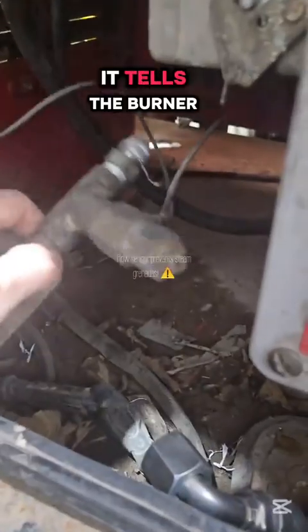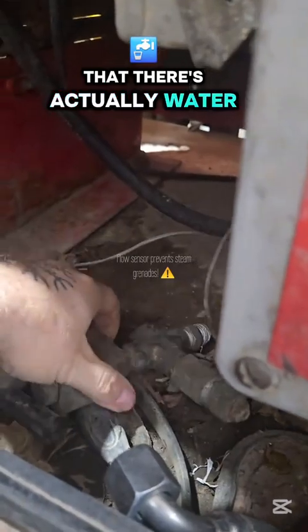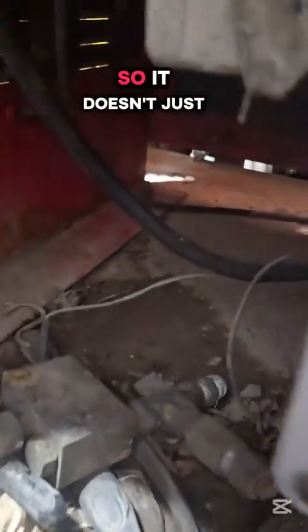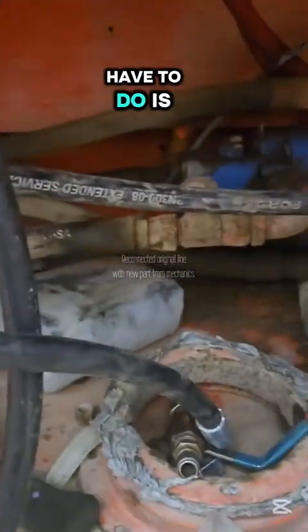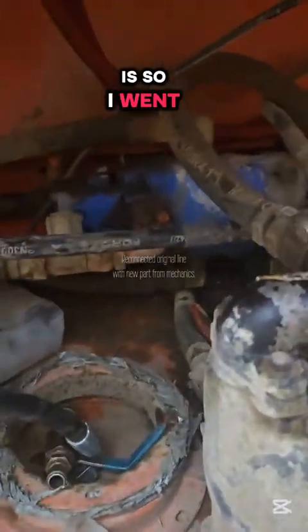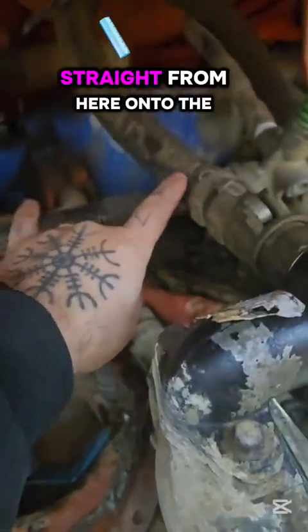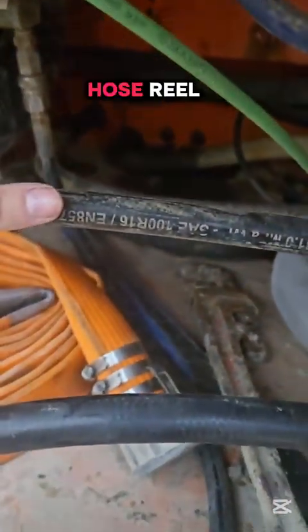Also disconnected that flow sensor completely. It tells the burner that there's actually water flowing through the line, so it doesn't just heat up until you have a steam grenade. So now what I have to do is, also what this does is, so I took that line off and I went straight from here onto the hose reel.